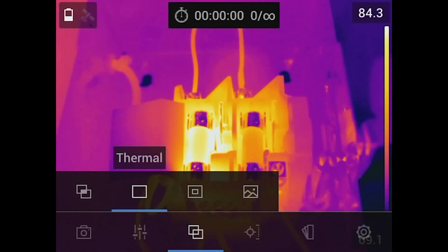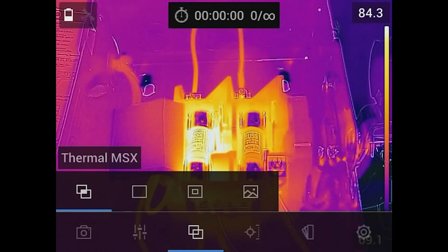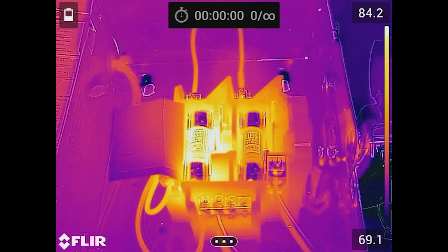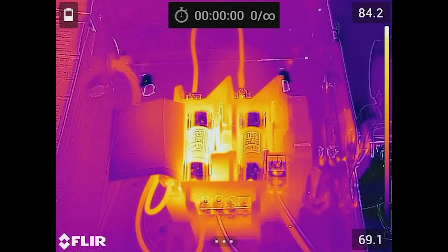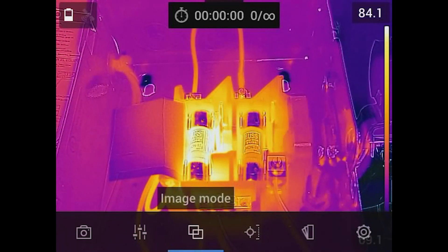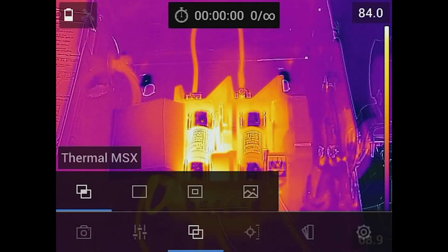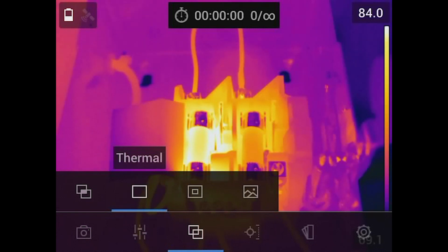As we move across, we can change the camera setting to our thermal MSX. This is where you can actually see the visible image raised or embossed on top of that thermal image. You could almost read all of the text on that fuse. Whereas if we turn off the MSX and just go to thermal, you'll notice it's actually disappeared. MSX is a really powerful feature that allows us to show the visible aspects of the image on top of the thermal.